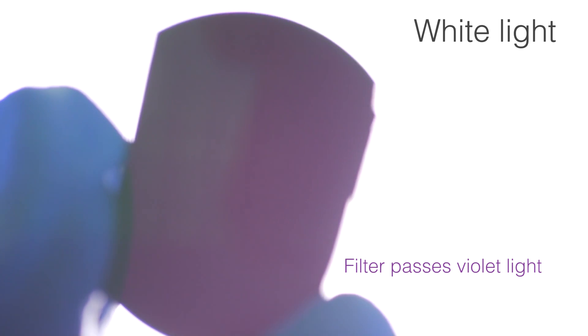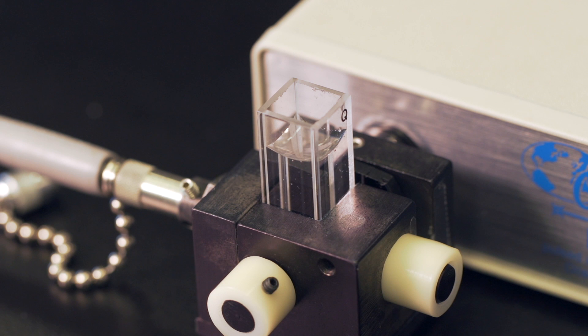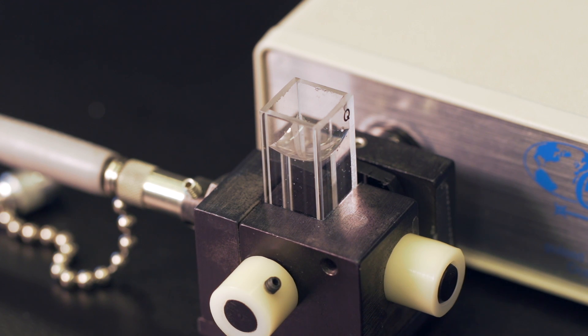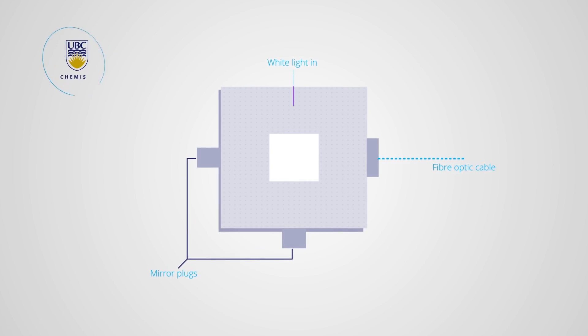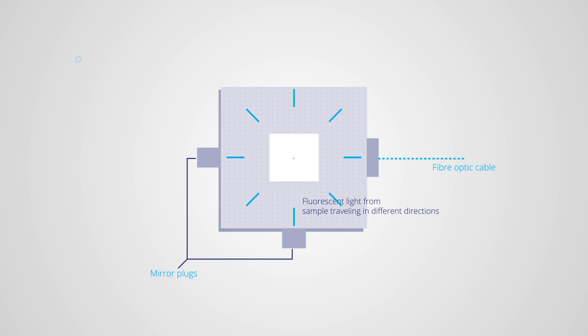The bandpass filter is a piece of colored glass that only permits particular wavelengths to pass through. For our analyte, the bandpass wavelengths are in the violet region of the spectrum, which can be seen when we hold the filter up against a light. As the light enters the cell, it encounters a cuvette filled with solution. The sample solution may absorb the light, and sample molecules become electronically excited. As a molecule relaxes back down to the ground state, it may emit a photon. Only a few of the photons that are emitted enter the fiber optic cable, since fluorescence occurs randomly in all directions — most don't reach the fiber optic cable and are lost.